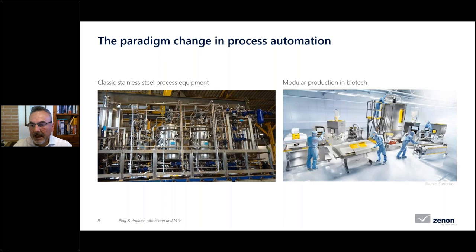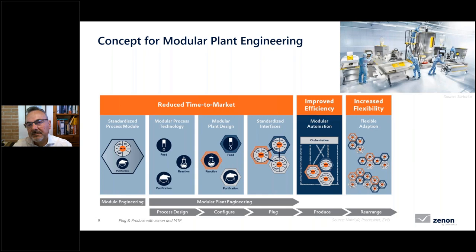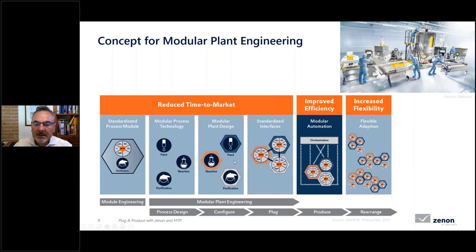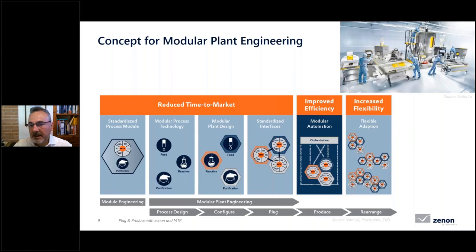In modular plant engineering, every standardized process module — like a filter, bioreactor, or doser system — has a common behavior and common interfacing from both mechanical and digital points of view. On top of these modules sits an orchestration layer that can detect which modules are present, read information coming from the modules, and command every module it has. We call this exactly orchestration.